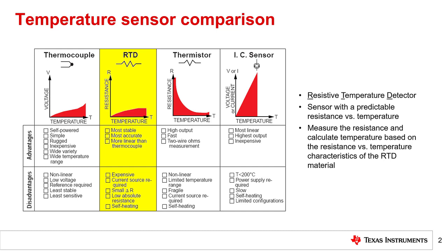Some of the benefits of an RTD is that they are the most stable and accurate temperature sensor. These two qualities enable RTDs to be used in many precision applications. RTDs are also highly linear, providing the user with a predictable relationship between sensor resistance and measured temperature. RTDs also have some disadvantages, such as requiring an external source to bias the sensor. Another challenge is that the change in RTD resistance is relatively small, resulting in a small output voltage.